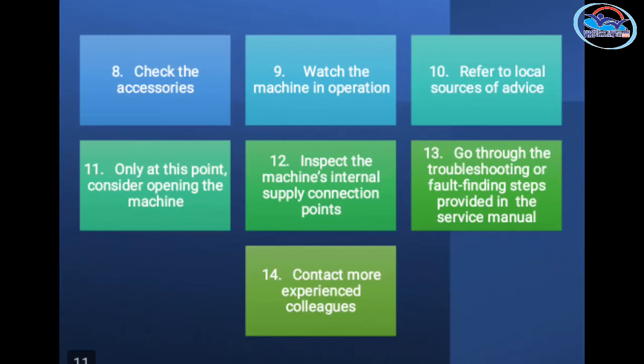If you have a complaint, this should be rectified. Only at step 11 should you consider opening the machine. At this point, inspect the machine's internal supply connection points, check the soldering section, and check the connection wires. If the complaint needs rectifying, go through the troubleshooting or fault-finding steps provided in the service manual.